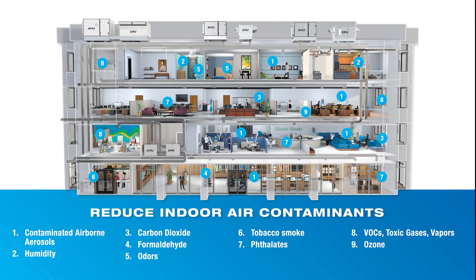Cognizant authorities like ASHRAE, the CDC, what we have in Europe, the DOE and the EPA—and we could continue through an entire list—agree that minimum ventilation as advocated by code is a start point. It's not necessarily what's considered a high performing building. When we look at controlling the spread of something like COVID-19, we have to increase the amount of outdoor air recommended by code to become a high performing building. So is that 30% above that? Is it 100% above that? Or is it a 100% outdoor air system?